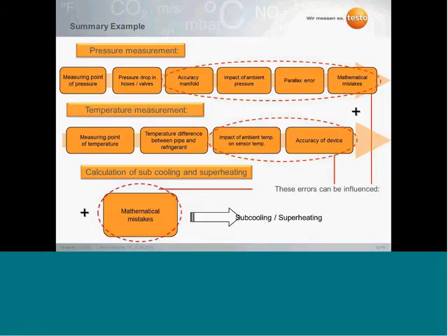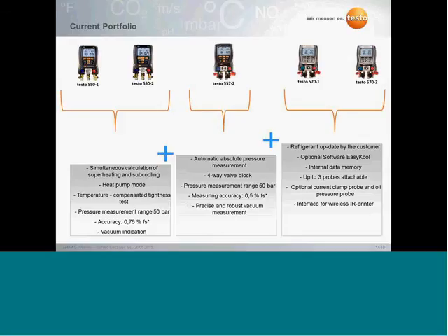Also an important point for Testo manifolds, if you see the impact of the ambient temperature on sensor temperatures: Testo is using a so-called surface temperature compensation. That means when measuring surface temperatures on a refrigeration system, the surrounding temperature is also measured by our digital manifold, and based on this, a recalculation or an adaptation of the measured surface temperature is done. This is also done by our electronic manifold. So that's the point why we think the digital manifold is the better solution to measure. And now to come to the new digital manifolds.